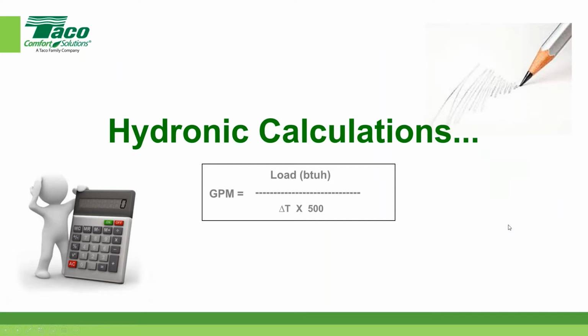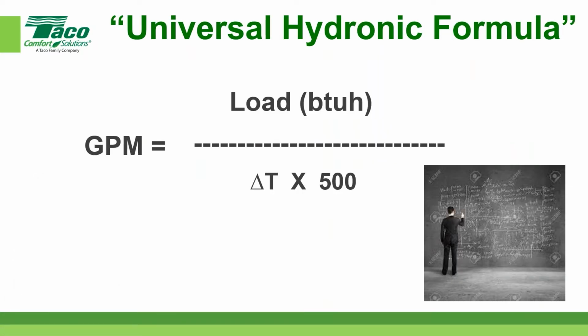Okay, we'll start with this hydronic calculation, a dual conversion formula, and we call it the universal hydronic formula. I'm not sure what everybody else calls it, but between a couple different companies I've worked for, we've made that pretty much known. But I like to go a little deeper and say, hey, it's a dual conversion formula as well. And this is what the next couple of slides will talk about. If we're solving for gallons per minute, this is what we're solving for, but it's based on the load that's in British thermal units. So BTUs and GPM, they have something that correlates, but they're two different things. And this is what I want you to understand. Gallons per minute is what we're solving for, but it's based on something that's a British thermal unit.